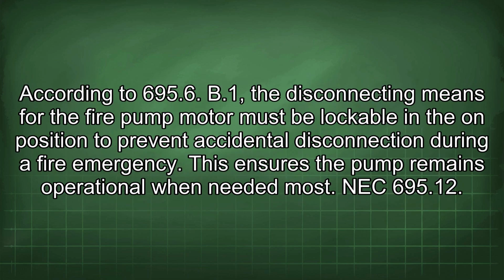According to 695.6(B)(1), the disconnecting means for the fire pump motor must be lockable in the on position to prevent accidental disconnection during a fire emergency. This ensures the pump remains operational when needed most.